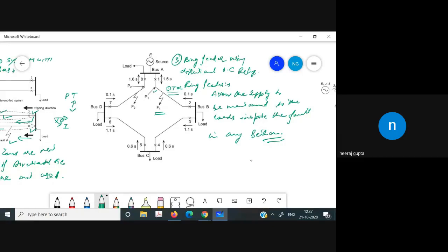We have the fault F1 due to the line cut open at point P1, and this makes the directional relay 2 operate, which is the remotest relay from the source, as we have seen in the DTOC type of relays. So the remotest relay in this case is 2, so it will operate first, and 2 is also closest to the fault as compared to 3 and 4.